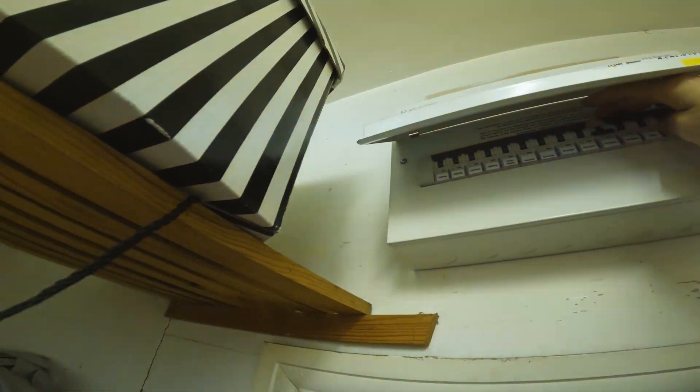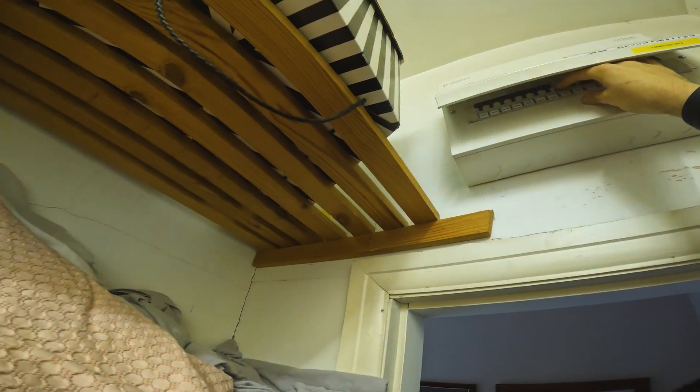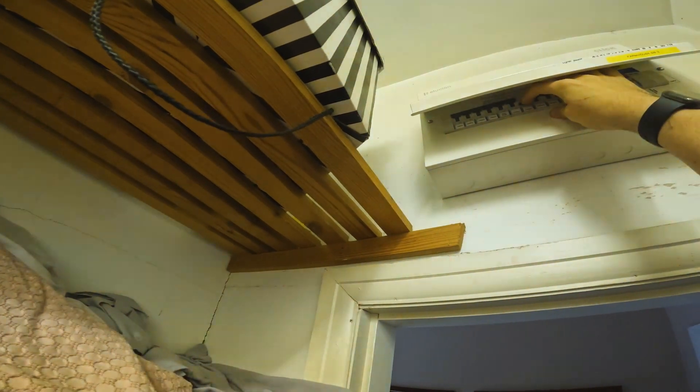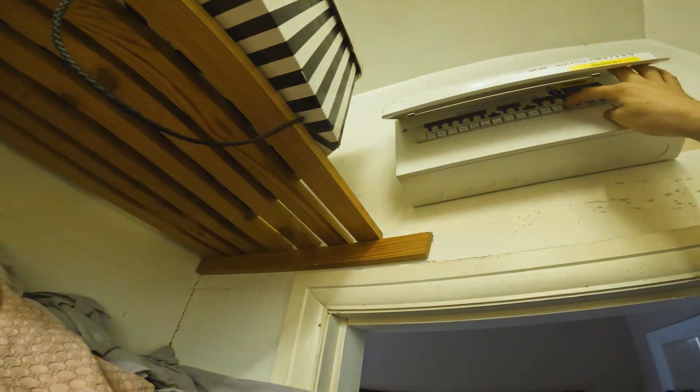One's off at the moment. Right, that's that one. Counting: one, two, three, four, five, six, seven — so that's circuit seven then. It's not wires, it's circuit seven. Find out what's dead. I'll do cookers next. That's circuit two. Right, I'll do lighting now. Lights are on.